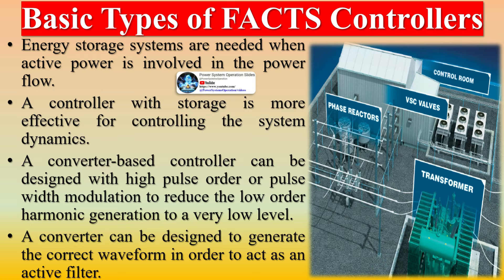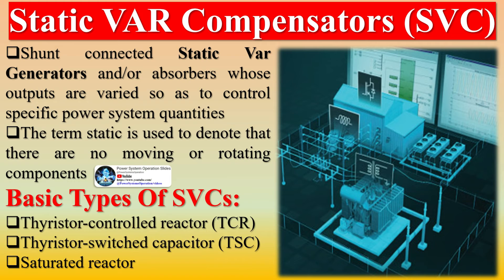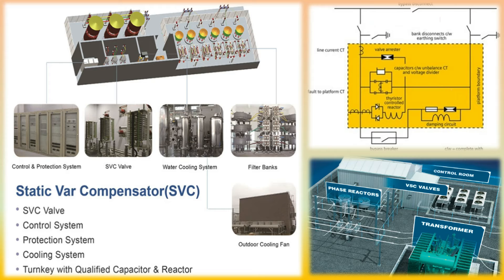Static VAR Compensators (SVC) are shunt-connected static VAR generators and/or absorbers whose outputs are varied so as to control specific power system quantities. The term 'static' is used to denote that there are no moving or rotating components. Basic types of SVCs include: thyristor-controlled reactor (TCR), thyristor-switched capacitor (TSC), and saturated reactor. A Static VAR System (SVS) is an aggregation of SVCs and mechanically switched capacitors or reactors whose outputs are coordinated. When operating at its capacitive limit, an SVC behaves like a simple capacitor.